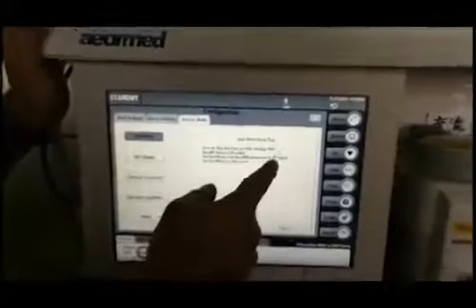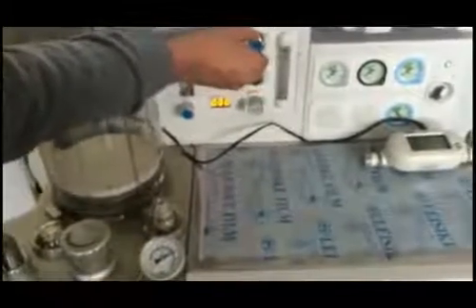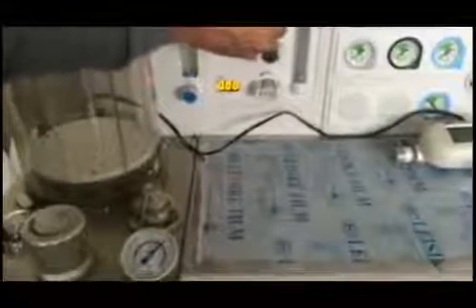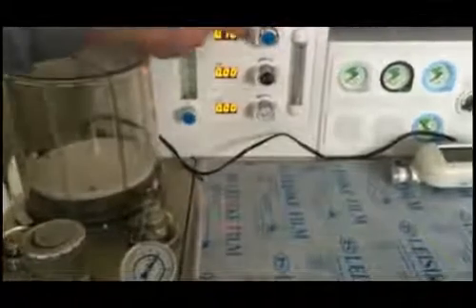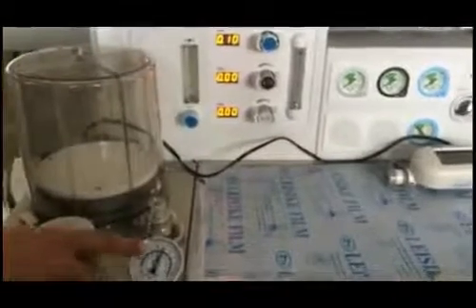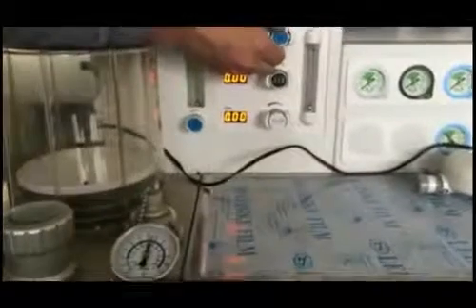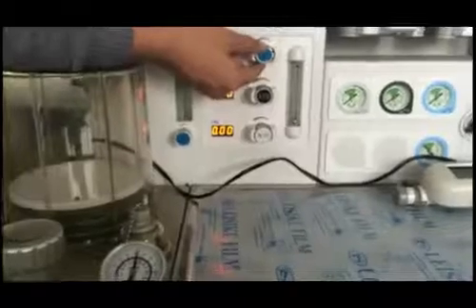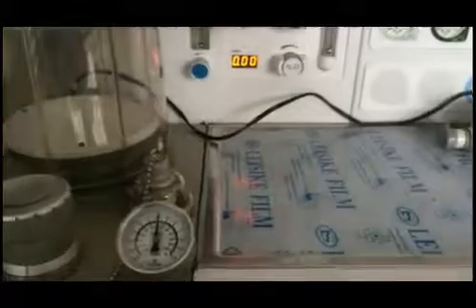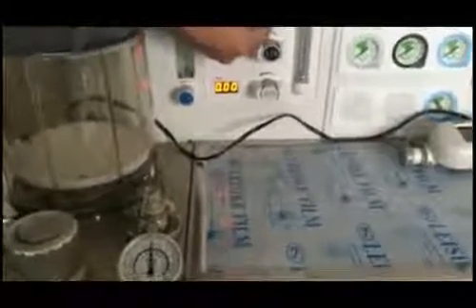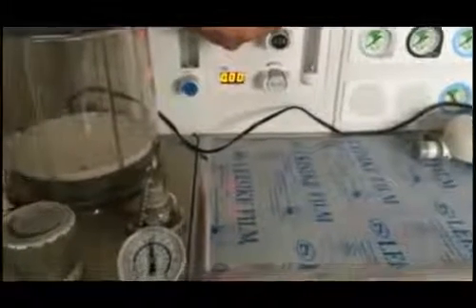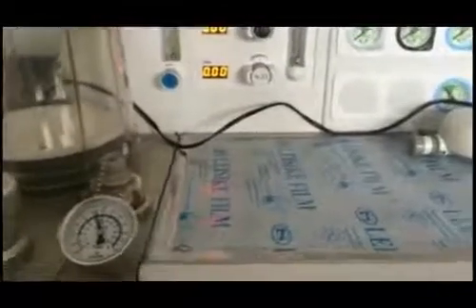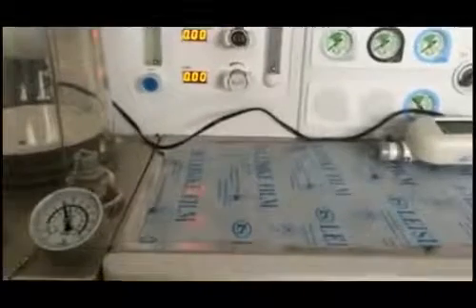The next step is to set the flow meter until the airway pressure is up to 30 cm of H2O. This is the airway gauge. By rotating the flow meter, we can achieve this pressure, which is 30. As you can see, I am rotating the flow meter while watching the airway gauge. As you can see, the airway gauge has reached 30.